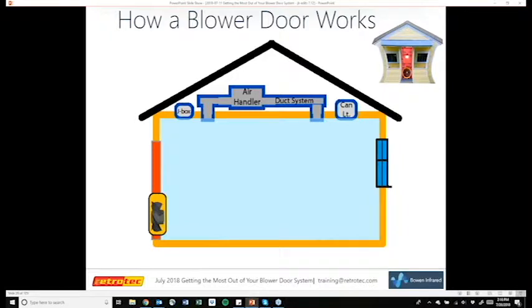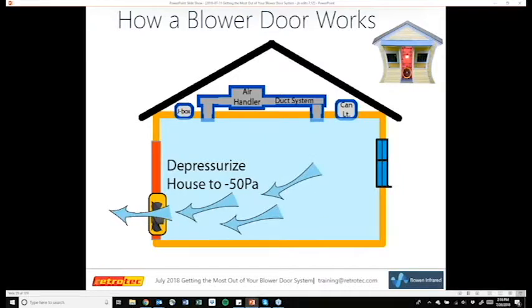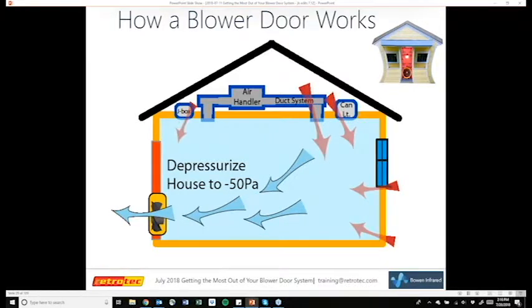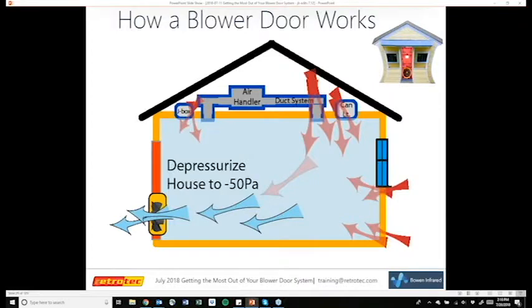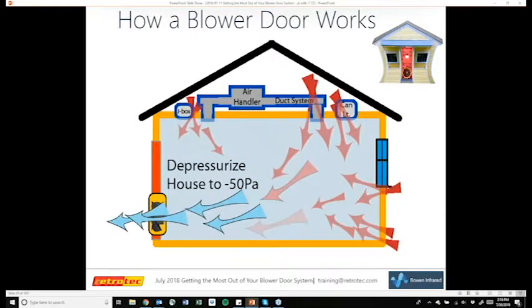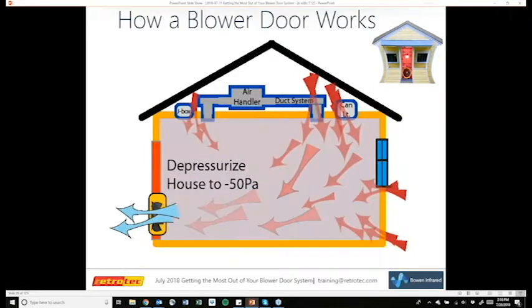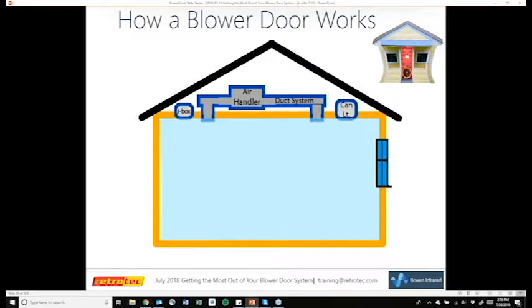So this is just a little simulation to show how depressurizing a house works, where the air comes in from, and how the blower door reads it. These red arrows are infiltration coming in. So basically what it does is it amplifies the infiltration of the house at a certain pressure, which is 50 pascal. That way it can know how bad it's leaking.